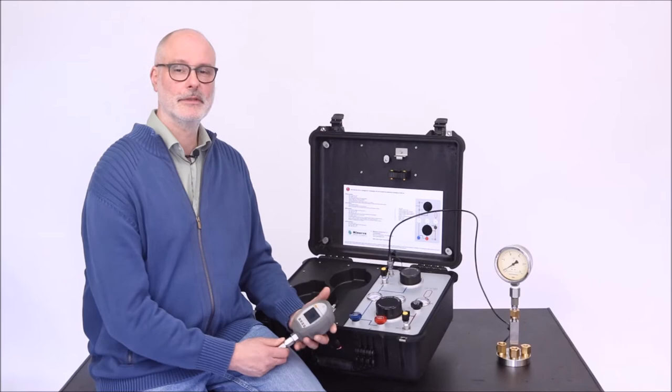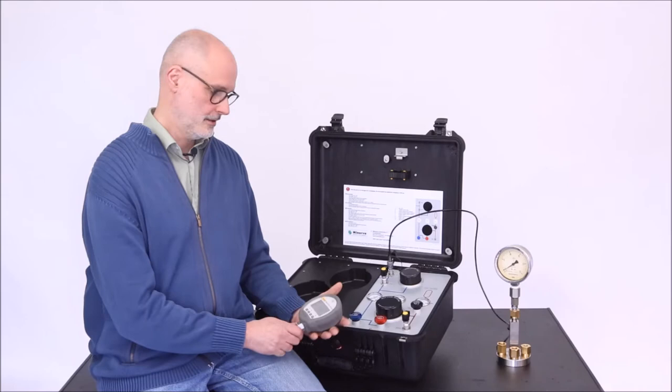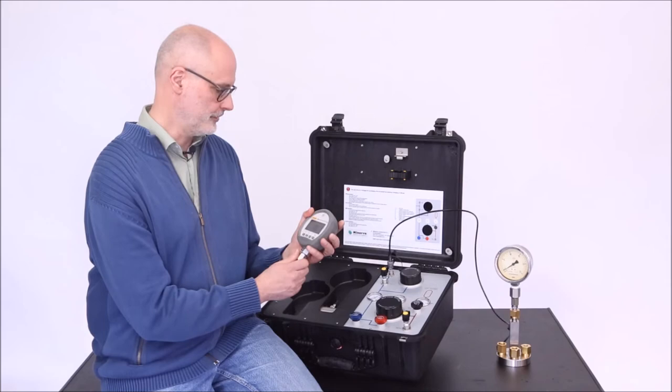So we've talked about the advantages of our Minerva Portable High Pressure Case. Now I want to show you how to set an accurate nominal pressure. I'm going to use a 2700G pressure reference and connect this to the swivel.